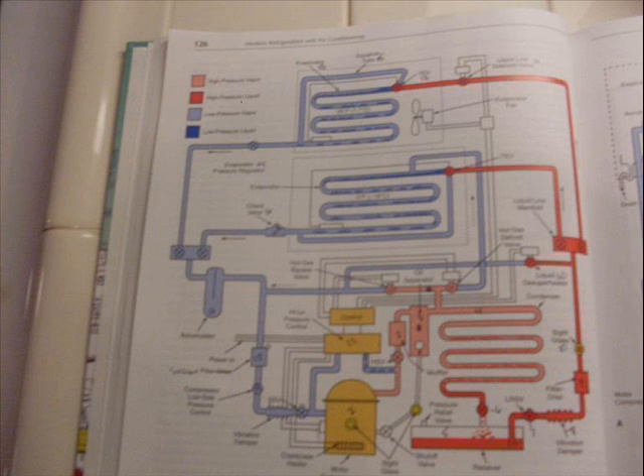Now, in your refrigerator at home, you have a heat exchanger. Probably not what you're thinking about, though. What they do is they'll actually take the capillary tube, they'll drill a hole in the suction line, and they'll put the capillary tube inside the suction line and run it all the way up to the evaporator inside the suction line. And then, right at the evaporator, it separates, so the cooling gases come back, and they go around the capillary tube all the way down the suction line on the way back to the compressor. And that is our heat exchanger.